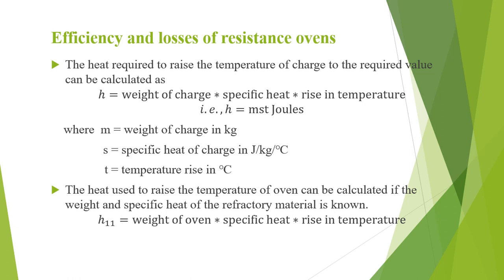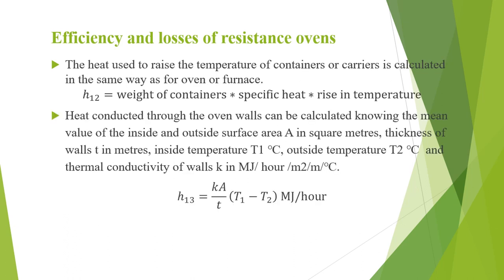If the oven is used continuously, this loss is negligible. The heat used to raise the temperature of containers or carriers, denoted H12, is calculated the same way: H12 = weight of containers × specific heat × rise in temperature. The container has to be heated every time the furnace is charged. Heat conducted through the oven walls, denoted H13, is given by H13 = K × A / T × (T1 − T2), where A is the mean surface area in square meters, T is wall thickness in meters, T1 and T2 are inside and outside temperatures, and K is the thermal conductivity.